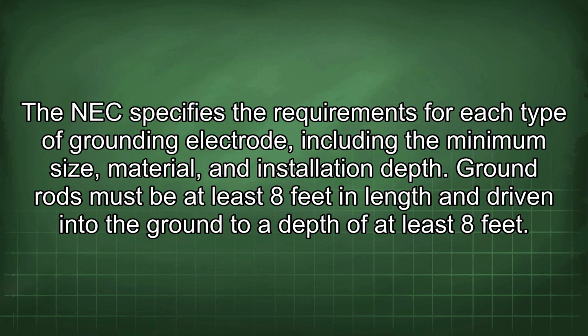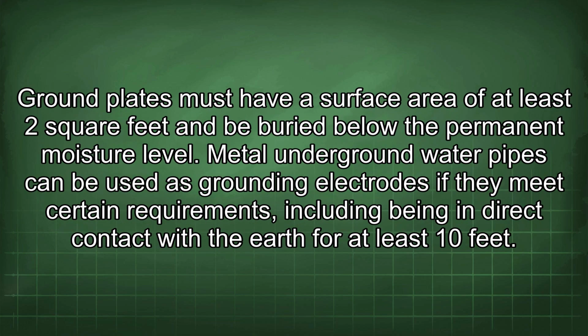depth. Ground rods must be at least 8 feet in length and driven into the ground to a depth of at least 8 feet. Ground plates must have a surface area of at least 2 square feet and be buried below the permanent moisture level. Metal underground water pipes can be used as grounding electrodes if they meet certain requirements, including being in direct contact with the earth for at least 10 feet.